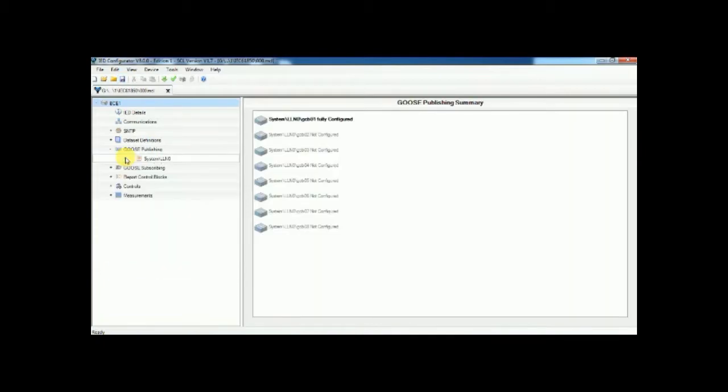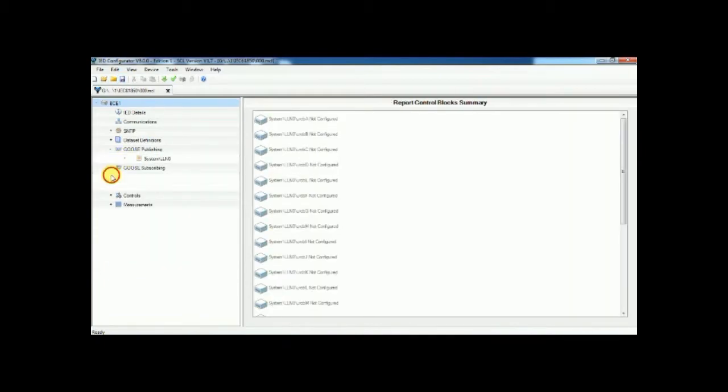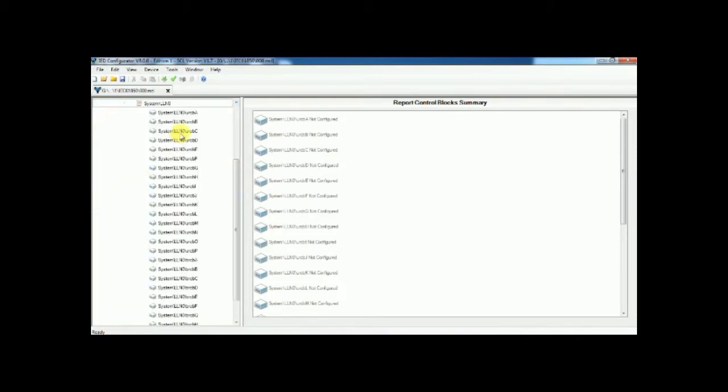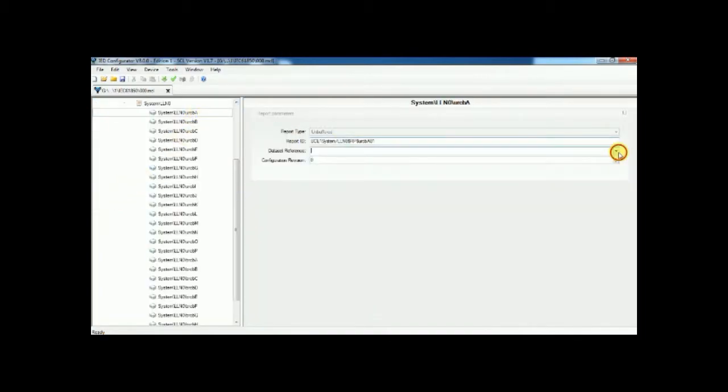One is the protection signal and another one is the relay binary input sheet. These 2 sheets have to be merged on report control. For each sheet make 4 report controls. Each one will contact with one client. So if you assign 4 report controls for each sheet, then one sheet can respond to 4 clients.